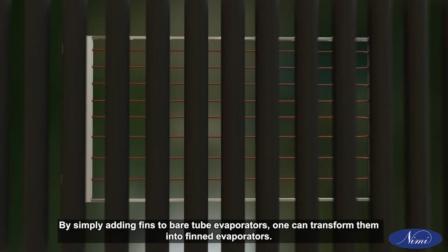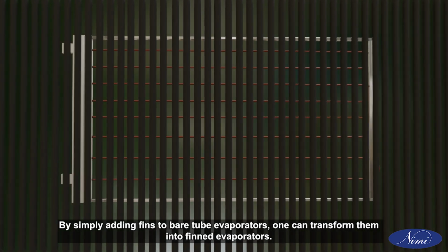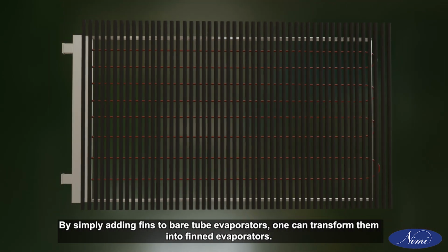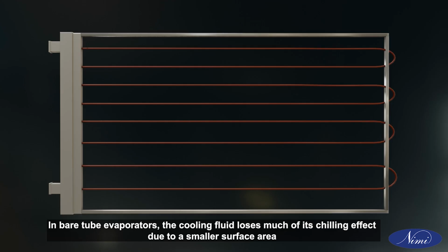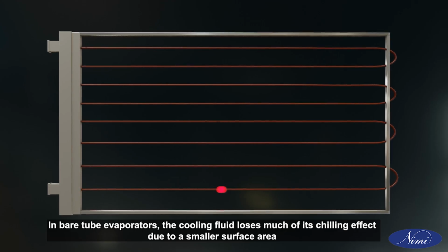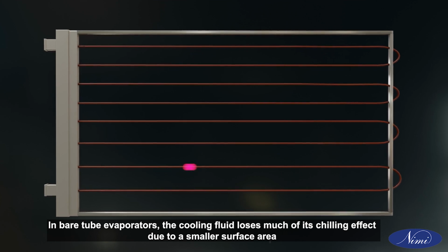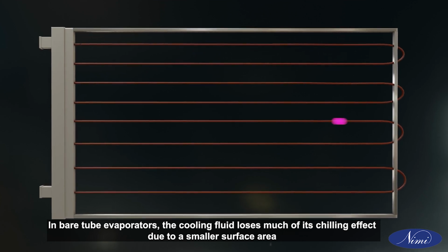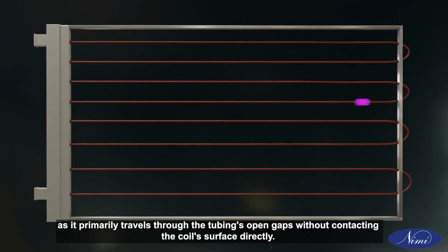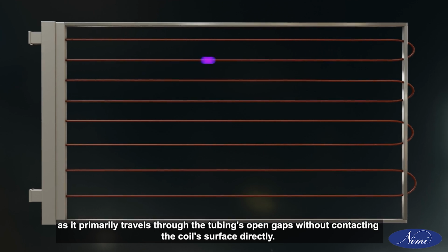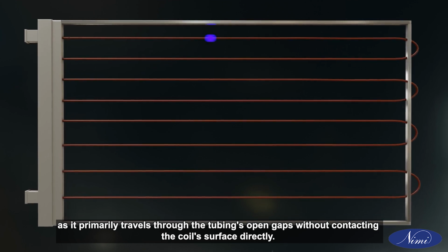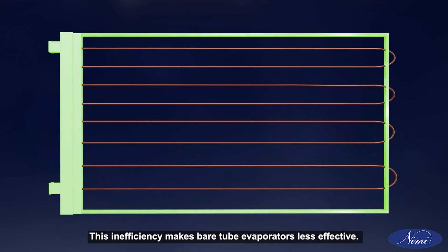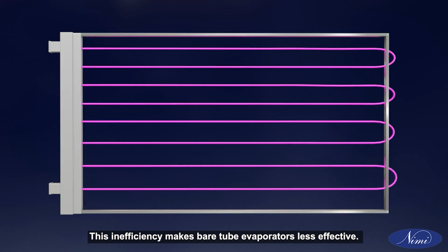By simply adding fins to bare tube evaporators, one can transform them into finned evaporators. In bare tube evaporators, the cooling fluid loses much of its chilling effect due to a smaller surface area, as it primarily travels through the tubing's open gaps without contacting the coil's surface directly. This inefficiency makes bare tube evaporators less effective.